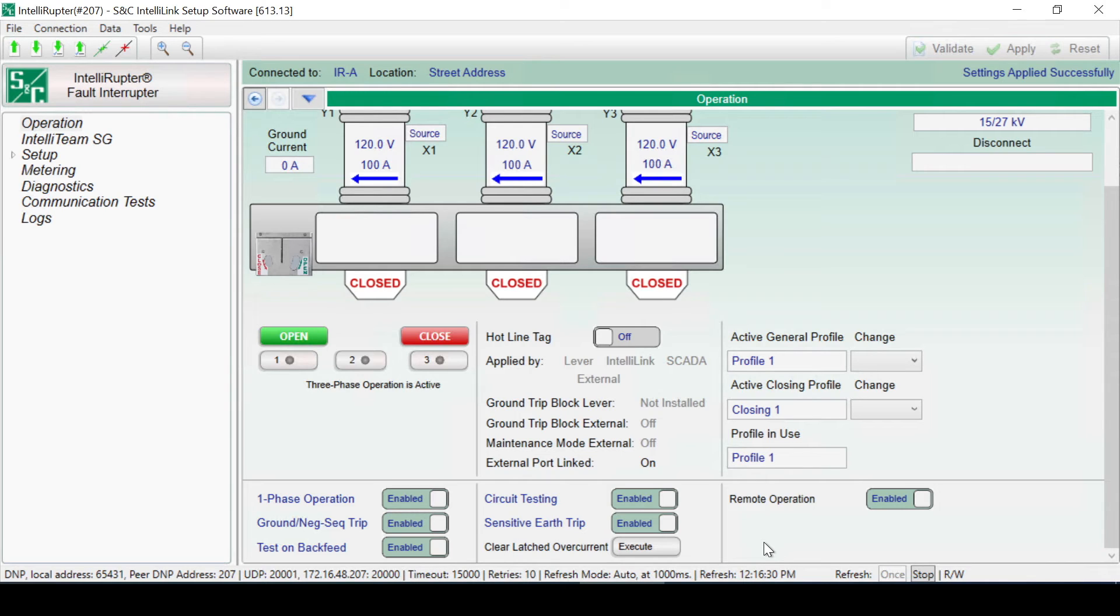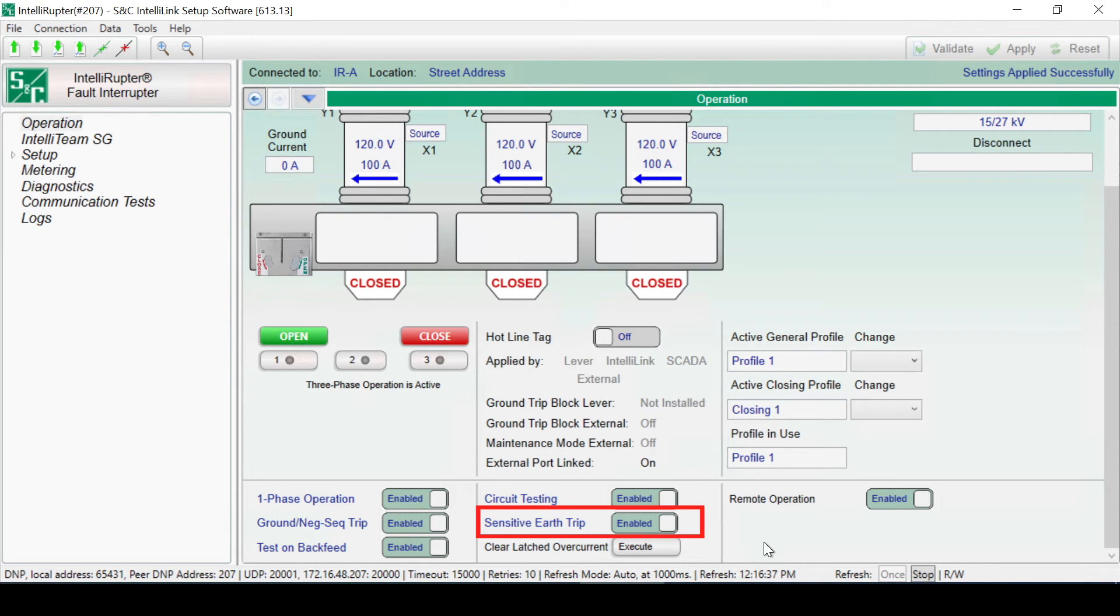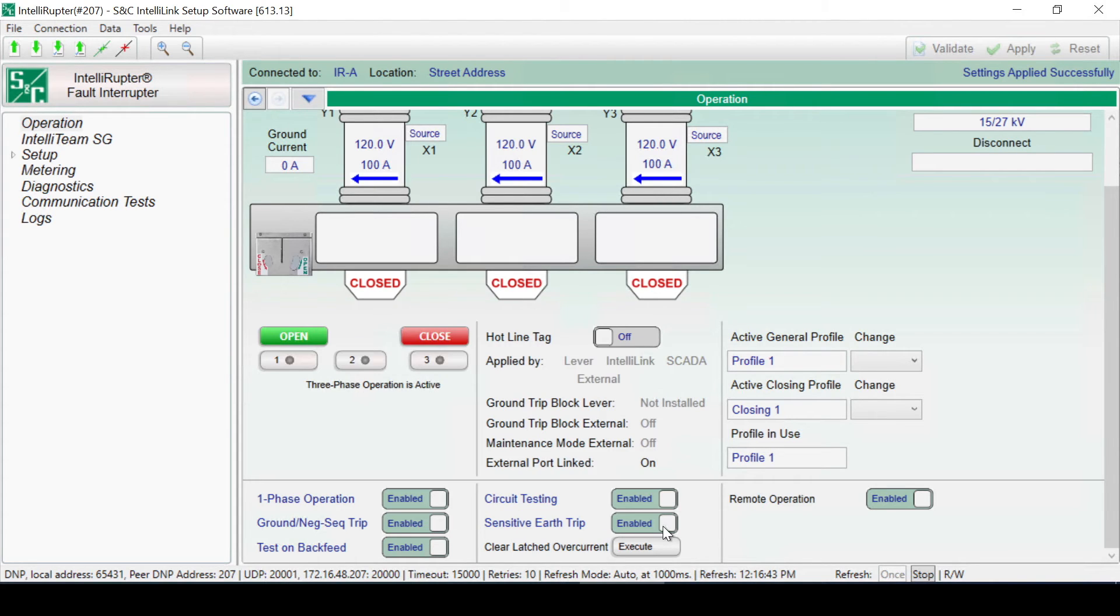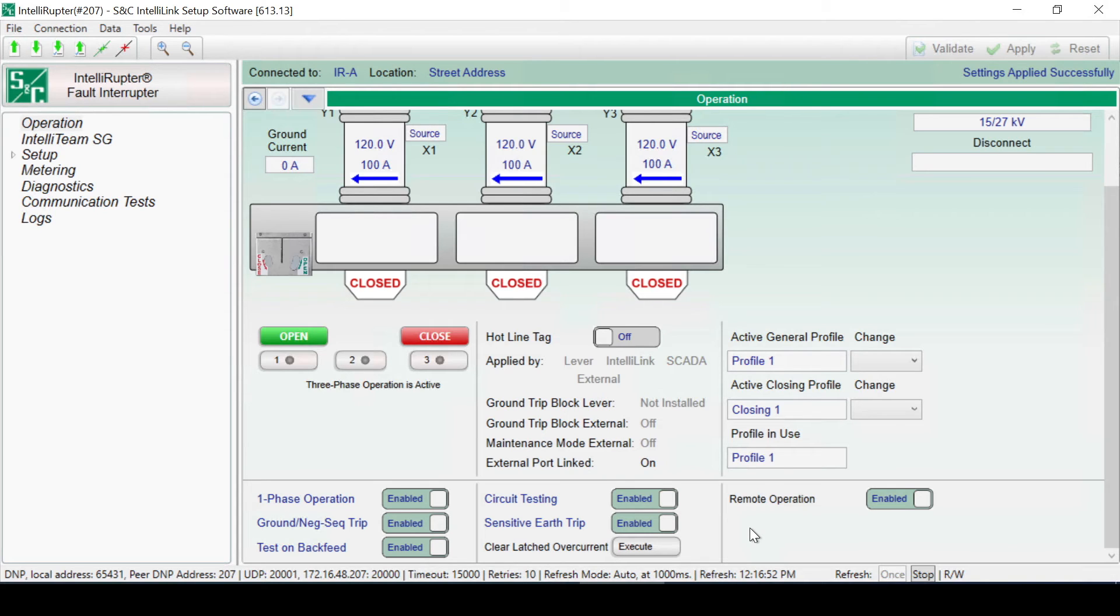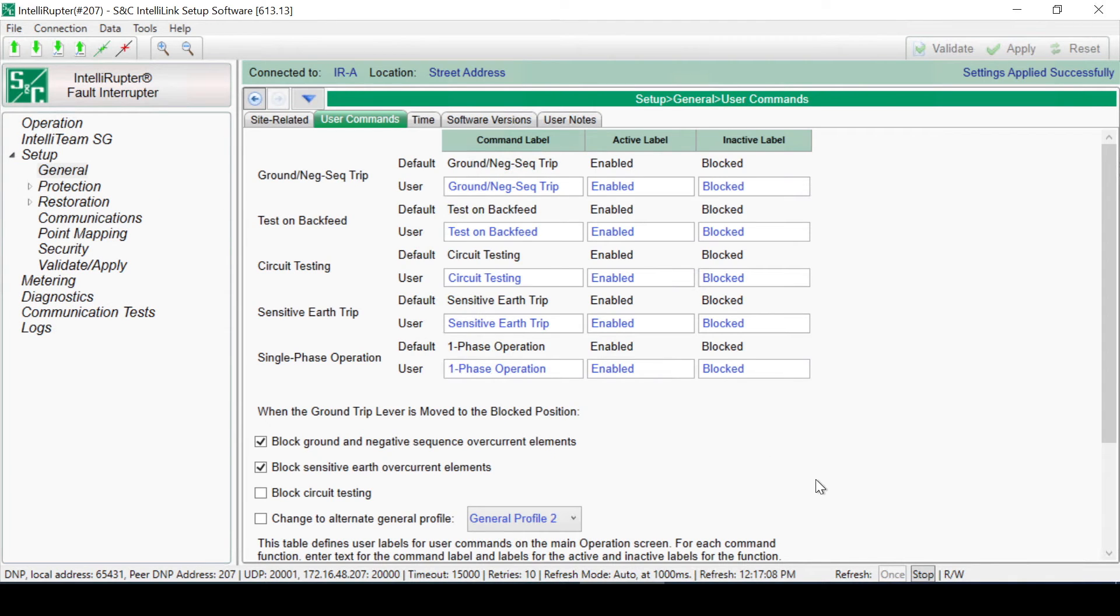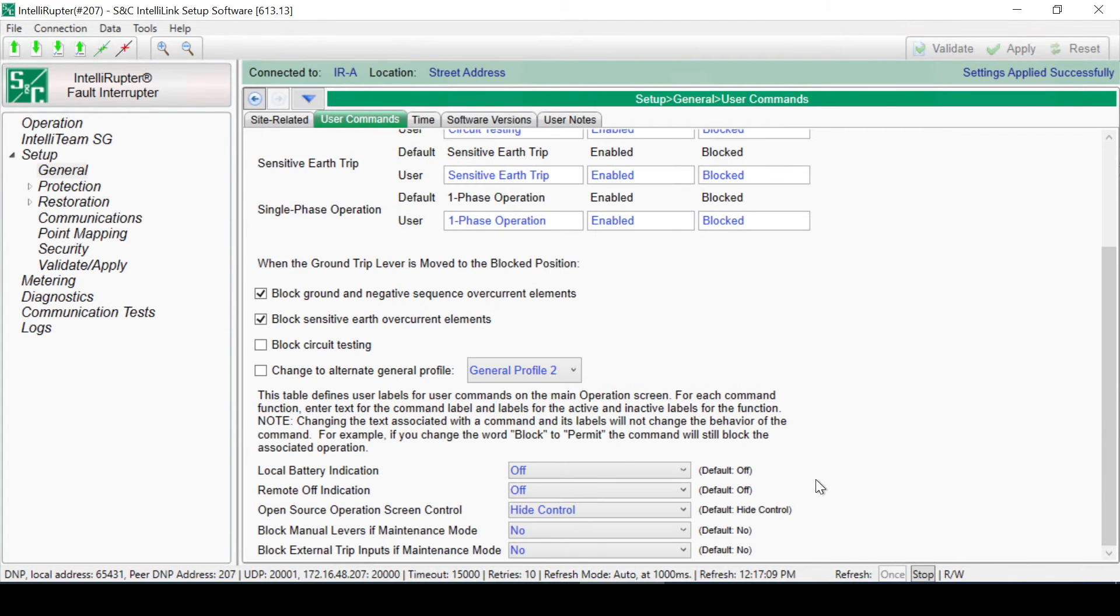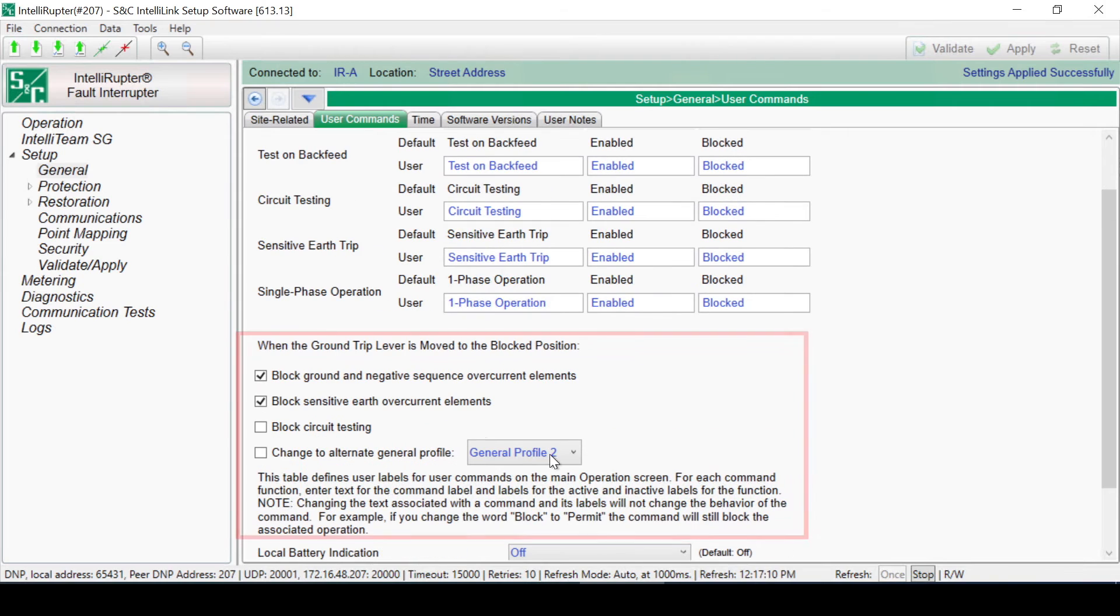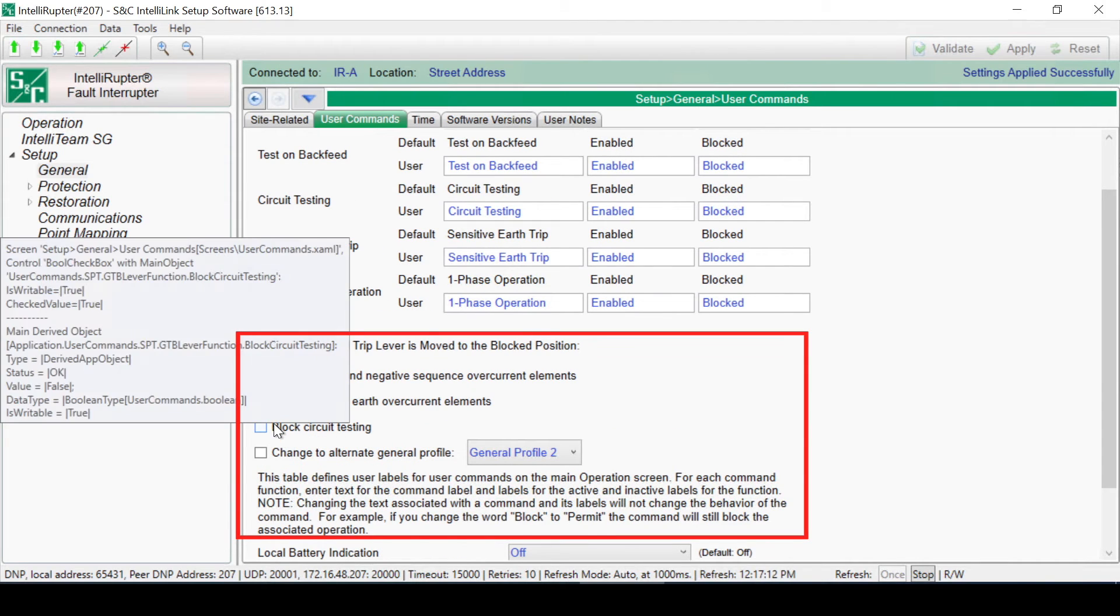Below that is a slide control for the Sensitive Earth Trip. This is a ground element used on three-wire systems to detect ground faults. It can be enabled or blocked using this control. Note that Sensitive Earth Trip is independent of the ground negative sequence trip. To determine whether the Sensitive Earth Trip will be disabled by the ground trip block lever, go to the Setup, General, User Command screen. There are several checkboxes used to define the functionality of the ground trip block lever. These selections can be independently enabled or disabled by clicking on the checkboxes.